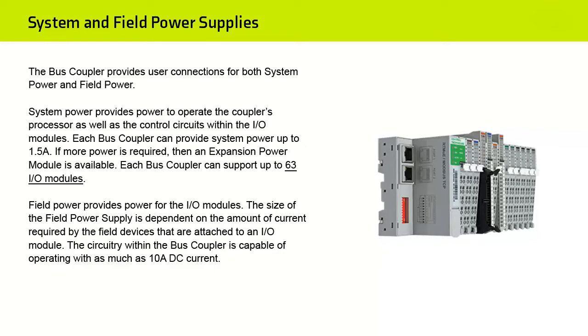Field Power provides power for the I/O modules. The size of the field power supply is dependent on the amount of current required by the field devices that are attached to an I/O module. The circuitry within the Bus Coupler is capable of operating with as much as 10 A DC current.